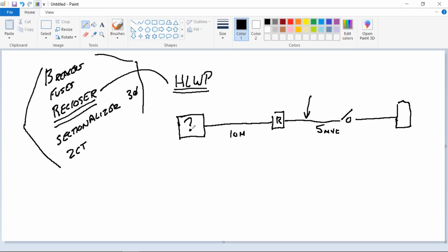Yeah. Okay, a recloser gets its own hotline work permit. No, then. Yeah, right. Modern reclosers right here have their own hotline work permit, and they function essentially the same, at least with the open and trip, as the breaker does. This one, as far as the fault occurrence, will recognize it first. It's going to give you an open. It never had time to make it down to the breaker, and we're talking a long distance of line to make it to the breaker.